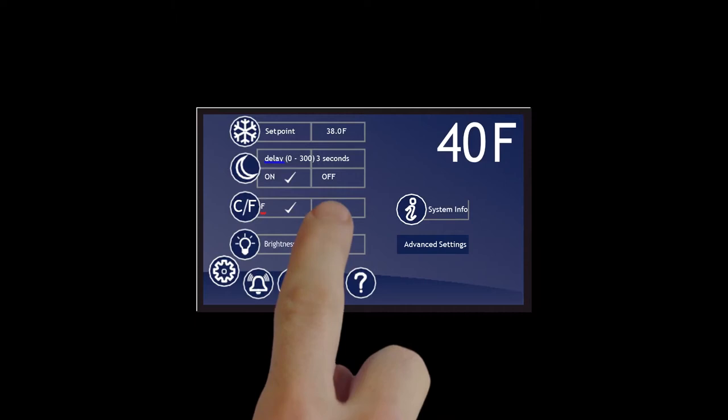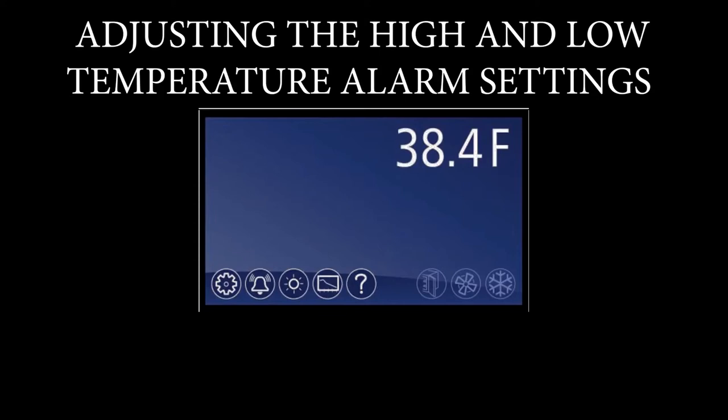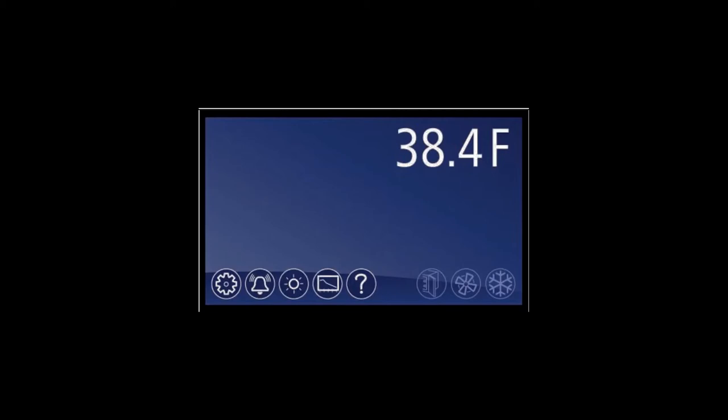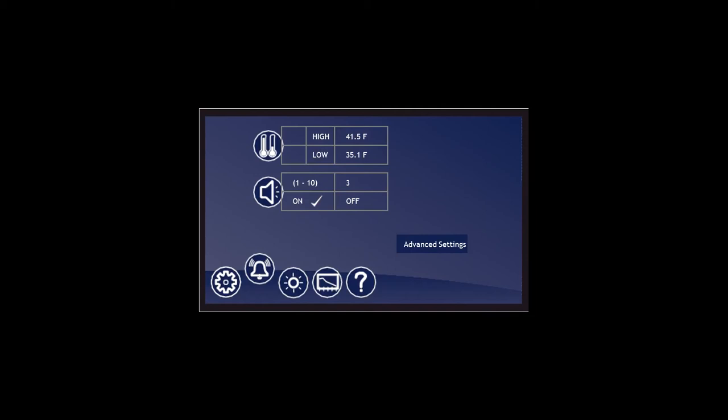Adjusting the high and low temperature alarm settings. This will only be required if desired by the end user. To change the temperature alarm settings, press the alarm icon which is located to the right of the Settings icon. To adjust the alarm values, simply touch the value in the box next to the label and either select the desired value on the keypad or use the arrows to scroll up or down to the desired value. To confirm the new value, press the check mark.